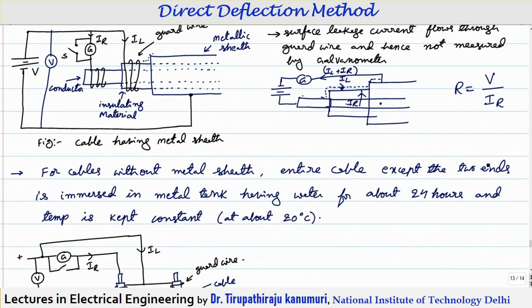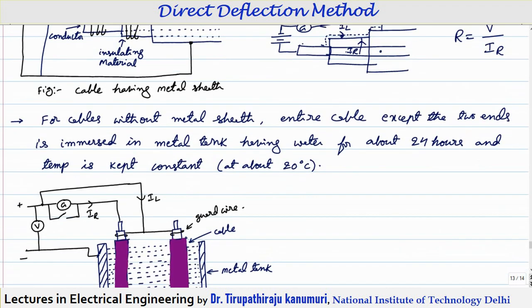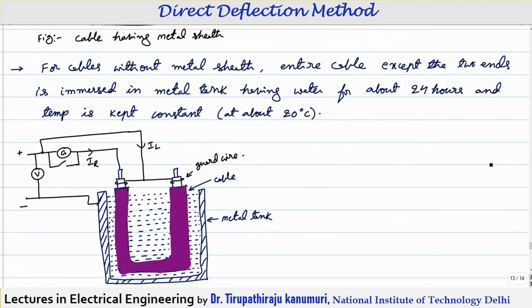If the cable does not have a metal sheath, we need to provide a negative terminal, which requires some metallic contact. For cables without a metallic sheath, the entire cable is dipped in saline water, which acts as a conductor. The cable is dipped in saline water and kept for 24 hours at a constant temperature of about 20 degrees. The saline water is in a metallic tank, which also acts as a conductor. The metallic tank acts as the negative terminal and is in contact with the saline water.